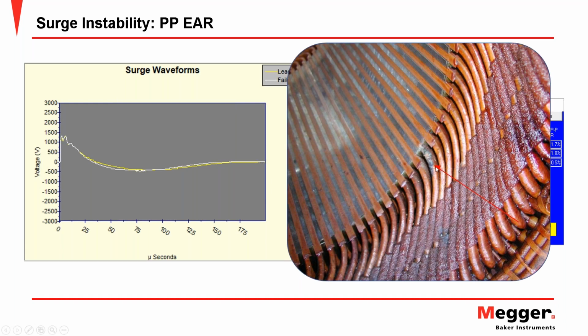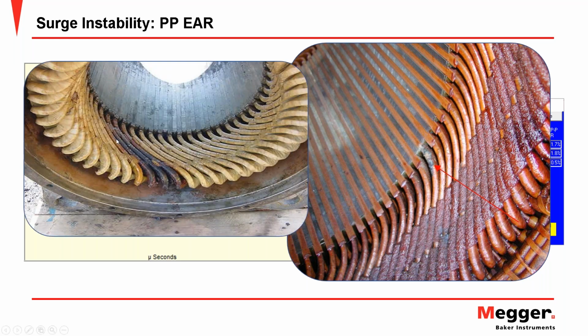So turn-to-turn faults that occur in the coil, before it burns through the ground wall or before it burns phase to phase, will have this high current flow internally, and you can see the localized heating that's occurred. It started out in just 2 adjacent turns and then slowly burns up these 3 coils till eventually this motor fails to ground as it exits the slot on that first coil I'm pointing to there. So PP EAR is a kind of telltale indicator that's going to help us mitigate this type of failure mode from causing a premature motor failure in our plant situation.